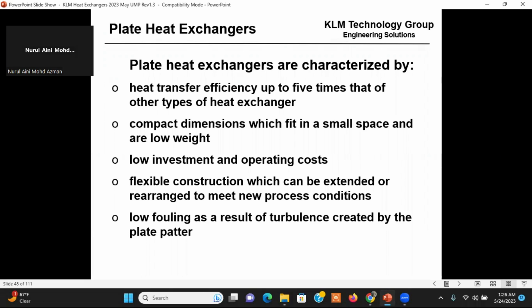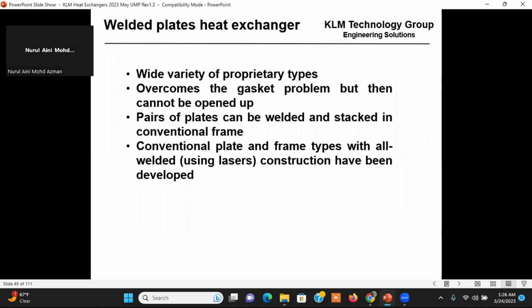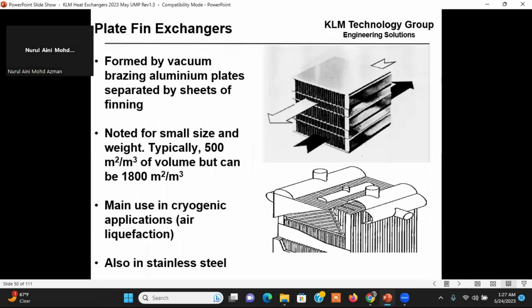So you've got a double pipe, you've got spiral, you've got shell and tube, you've got plate heat exchangers, and then you've got welded plate heat exchangers. Now these are typically for cryogenic services, and so they're welded together. They can't be opened up, so they must be very clean services. So you might do propylene refrigeration with ethane, and they typically look like this. They're typically welded together. They're very efficient. They have a lot of surface area, and so for cryogenic applications, air separation, for natural gas plants, for ethylene, you'll see a lot of these plate fin exchangers.